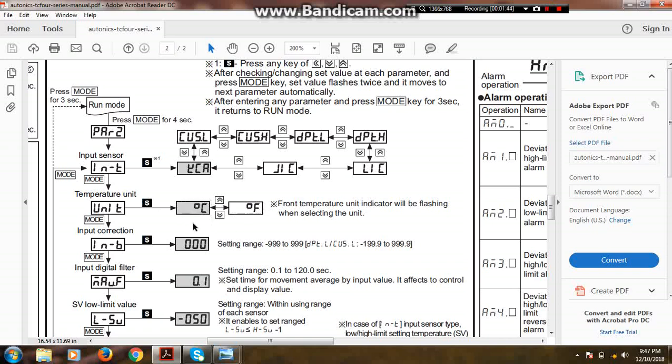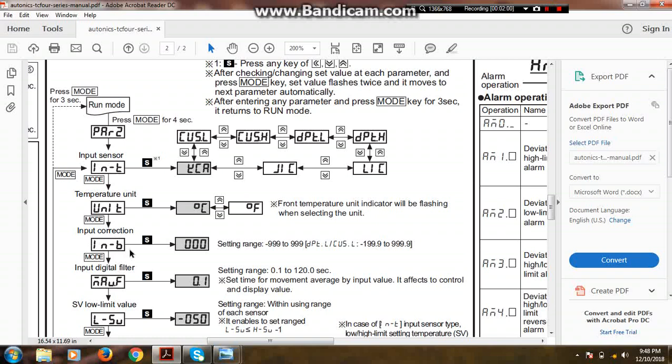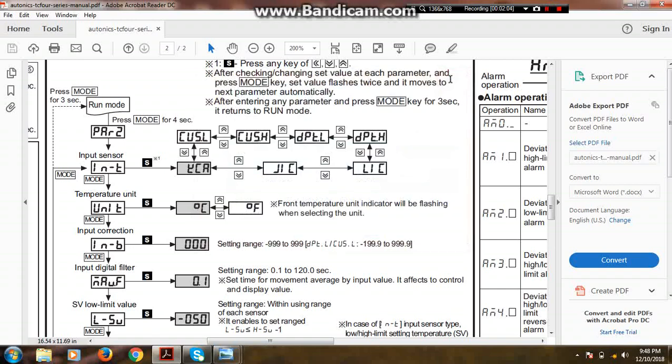The third most important parameter is input correction, IN-B. This parameter is used for temperature calibration purposes. I will quote an example here for better understanding of calibration procedures. Suppose our temperature process value is 40 degrees Celsius. If we want to increase the process value by 4 degrees Celsius, then we will add 4 in IN-B, our input correction parameter.